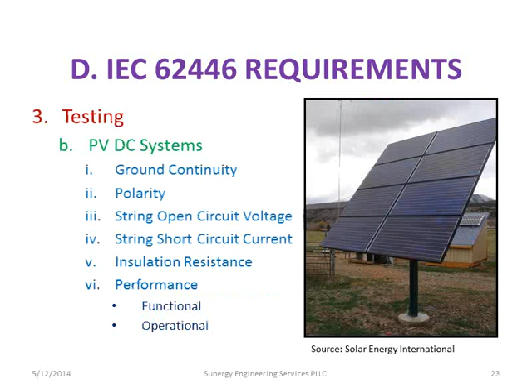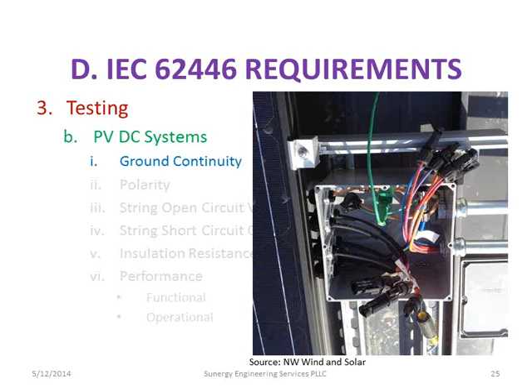And now comes the fun part, the stuff we do on the DC side. So this is a picture from a training. Was this last year, Kevin? It was over a year ago, wasn't it? We did training with Northwest Wind and Solar. And what we're actually doing is the ground continuity check. We're checking from the array, some surface on the array, either the rail or the frame of the array itself, and we're testing that going back to the grounding system. So we're running a wire from the grounding system to the array, and then we're running it through our meter to get an actual resistance measurement.